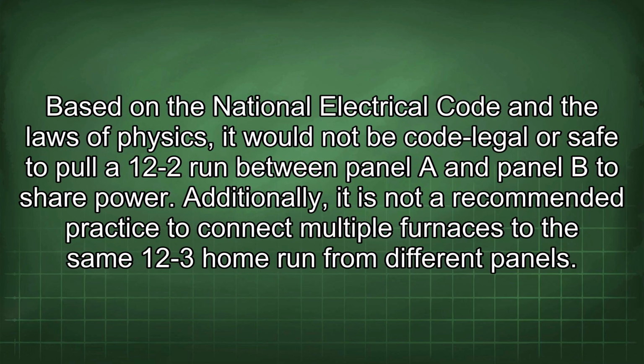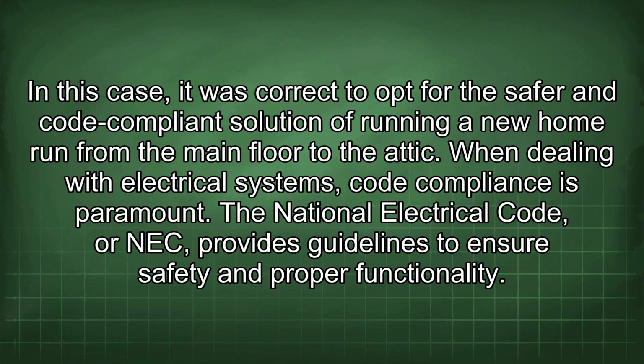Based on the National Electrical Code and the laws of physics, it would not be code legal or safe to pull a 12-2 run between panel A and panel B to share power. Additionally, it is not a recommended practice to connect multiple furnaces to the same 12-3 home run from different panels. In this case, it was correct to opt for the safer and code-compliant solution of running a new home run from the main floor to the attic.